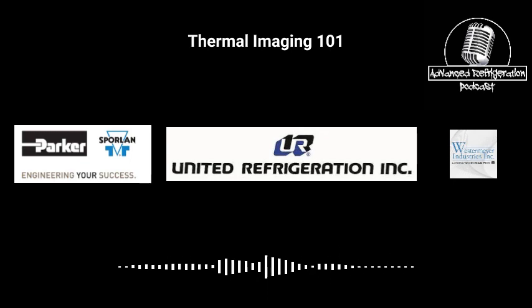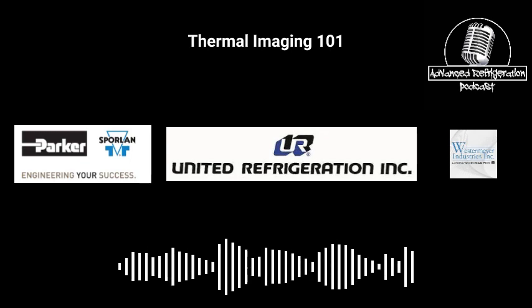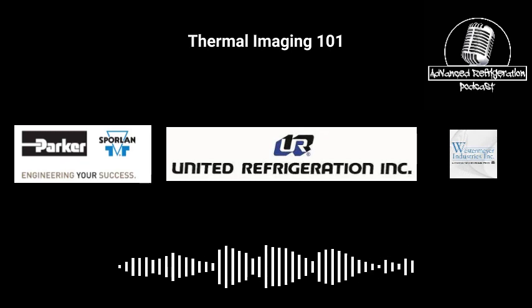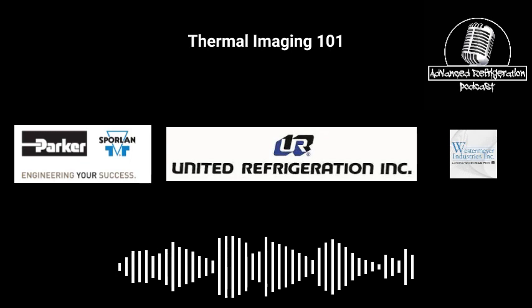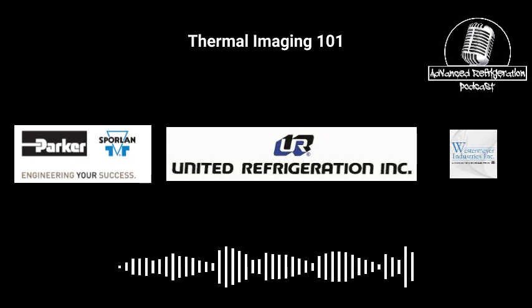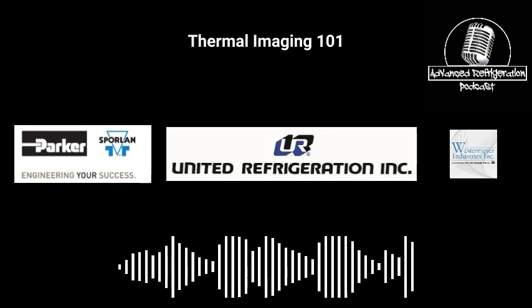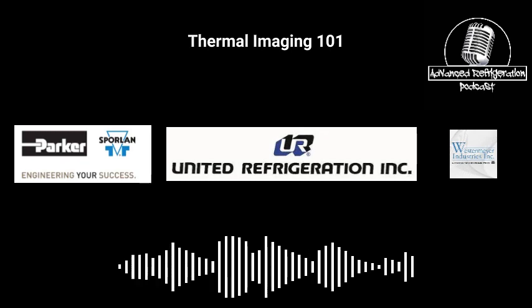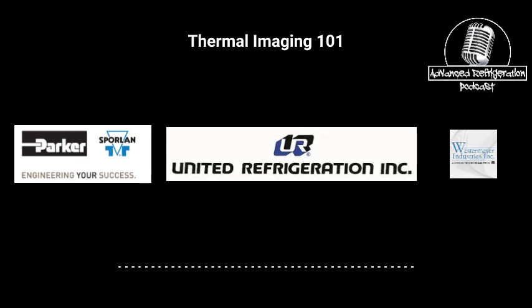You're working on frame heaters — say an Anthony frame might have five to seven heaters in it. You'd either have to rip all the mullions off to figure out what heater's doing what, or now with this thermal imager you can just shoot the frame and see, okay, doors 2 and 3 — those heaters aren't working, the inner heaters aren't working, but all the others seem good. So I'll just pull doors 2 and 3 and check those heaters instead of pulling all the covers off. Because anytime I pull those black covers off, I spend more time cussing and hating my life trying to clip them back on than anything else — you set them down, they bend slightly, and then they won't go back together, and you just hate everything.